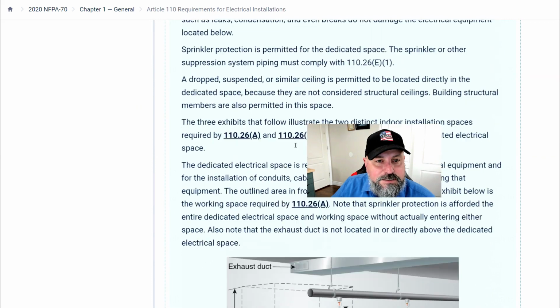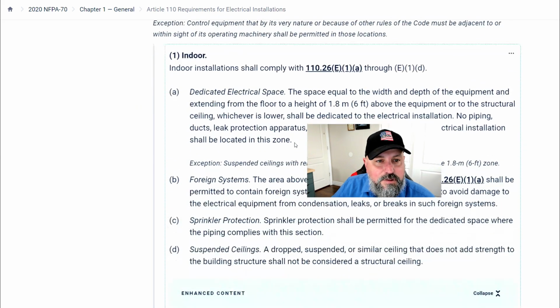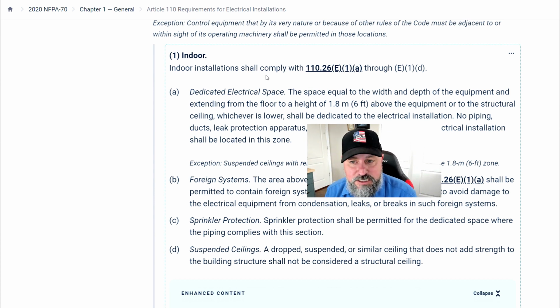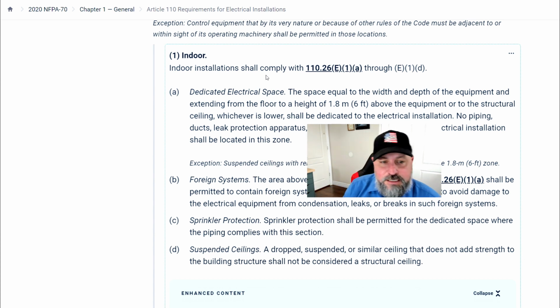So, dedicated workspace, there it is. Indoor installations shall comply with 110.26(E)(1)(a) through (E)(1)(d). Dedicated electrical space: the space equal to the width and depth of the equipment and extending from the floor to a height of 6 feet above the equipment or to the structural ceiling, whichever is lower, shall be dedicated to the electrical installation. No piping, ducts, leak protection apparatus, or other equipment foreign to the electrical installation shall be located in this zone. Exception: suspended ceilings with removable panels shall be permitted within the 6-foot zone.